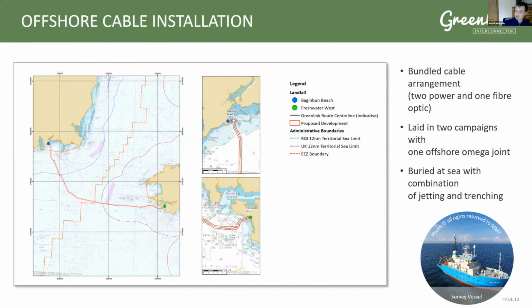Then on the offshore side of things, we're using a bundled cable arrangement. So the two power cables and one fiber optic cable are being bundled together and buried along the seafloor, along the route that you see here. This cable will be buried in two campaigns, and the cable will be jointed together after the end of the two campaigns in the middle of the ocean. It'll be buried with a combination of jetting and trenching.